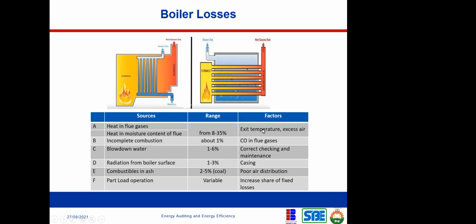So the exit temperature is high. Okay, now you are going to see another thing, excess air. When you add too much excess air, right? What that means is that you're also going to have higher heat that is going out from here. And that's what I was trying to explain the other time when I was talking about when you insert your probe to measure the characteristics of the gas that is going out from your stack here, right? So if you put that probe and you find out that the temperature is so high, what that tells you is that maybe you're adding too much excess air. So too much excess air will just push more of the heat that should have been absorbed by the water. It will just push more of that heat into the stack, and it will all escape into the environment.